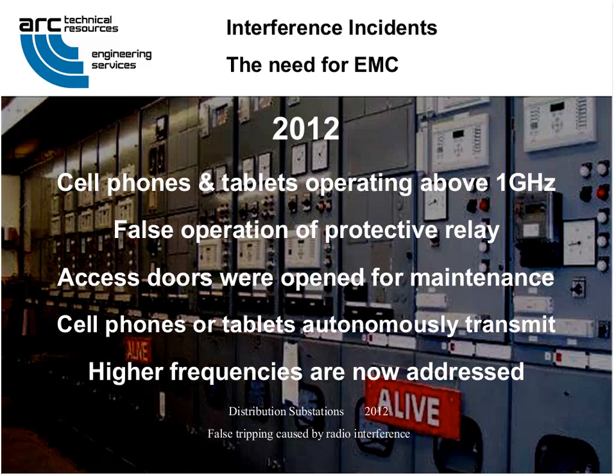With the advent of cell phones and tablets that operate above a gigahertz, they're clocked at frequencies above these older IEEE standards, up to 3.5 gigahertz now. New RF hazards have arisen. Then there were reports of false operation of a protective relay when its access door was open for maintenance. There's that story about the access doors again. Open for maintenance while a nearby cell phone or tablet transmits autonomously. The user doesn't have to tell his tablet or cell phone to do something, it just does. This testing gap at higher frequency is now addressed in IEEE 1613.1, completed in 2013, for the EMC testing of utility communications and networking equipment, which I'm going to talk about today.